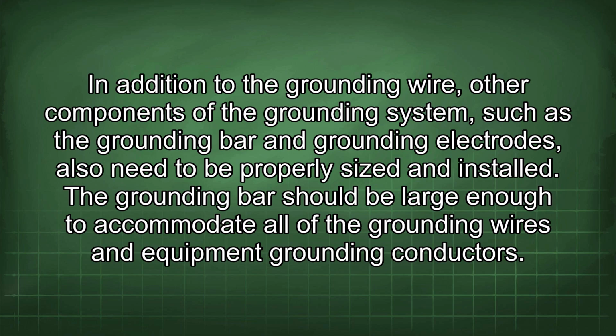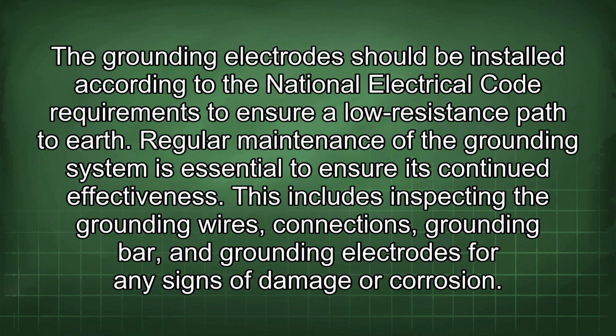The grounding bar should be large enough to accommodate all of the grounding wires and equipment grounding conductors. The grounding electrode should be installed according to the National Electrical Code requirements to ensure a low resistance path to earth. Regular maintenance of the grounding system is essential to ensure its continued effectiveness.